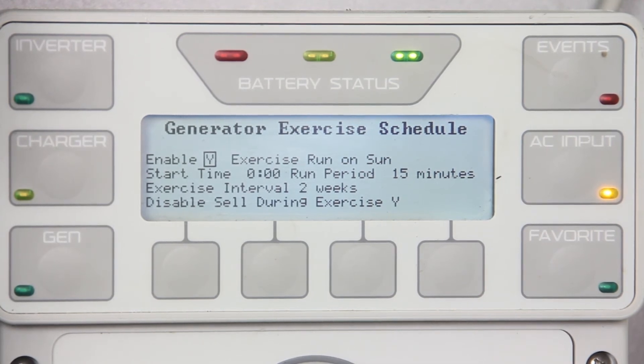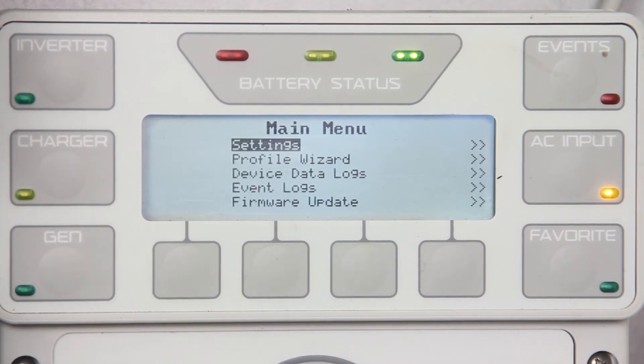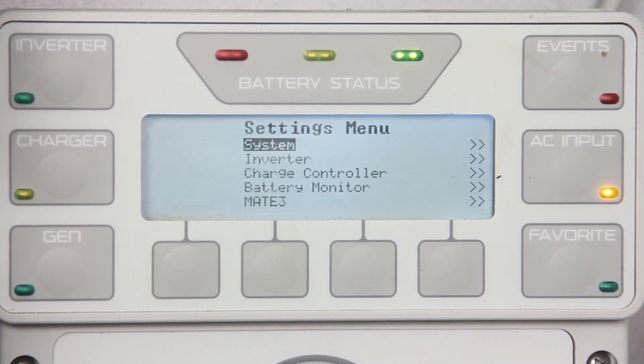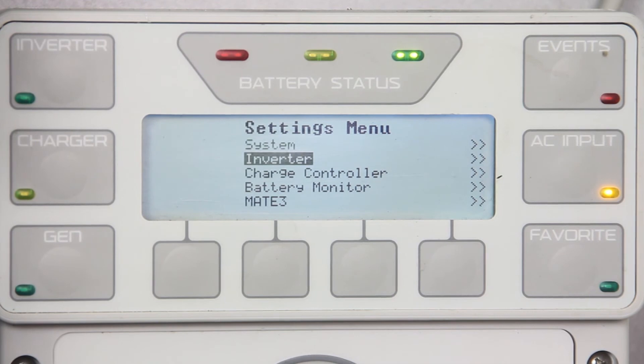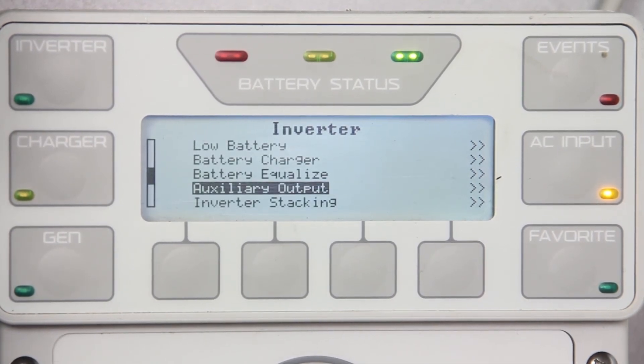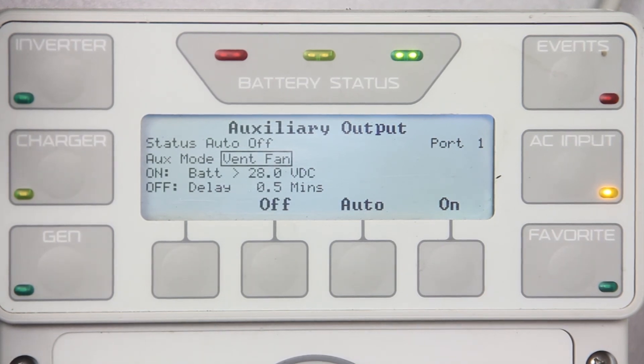Alright, we are done programming the AGS settings. Press top once. To prevent any conflict with auxiliary settings, we need to adjust the auxiliary function of the device that we are utilizing to power the GenStart relay. From the main menu, go to settings, then inverter, then auxiliary output. For the radian inverter chargers only, you have the option for auxiliary 12 volt or auxiliary relay. Select aux mode and change it to vent fan and adjust the voltage to the highest number.